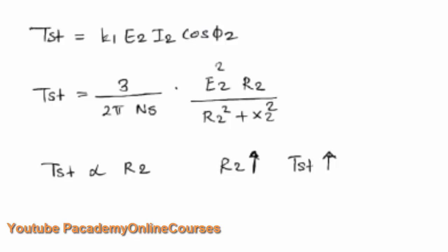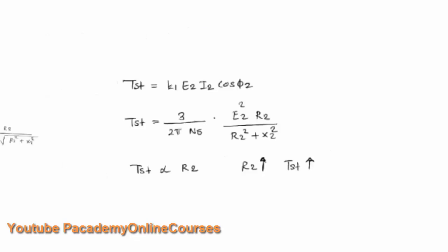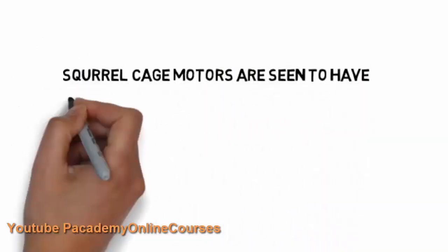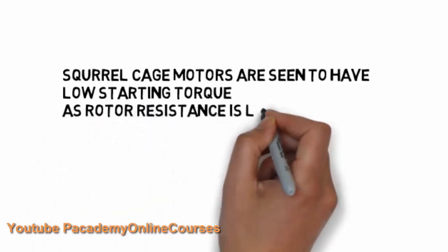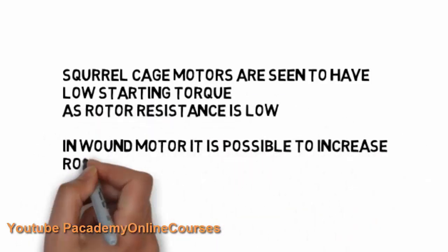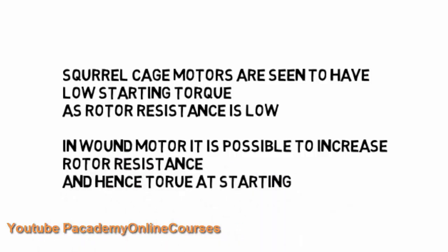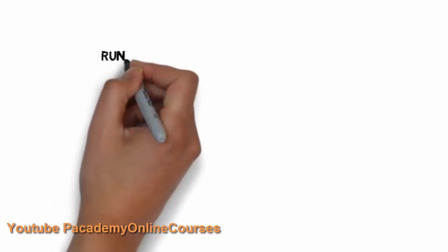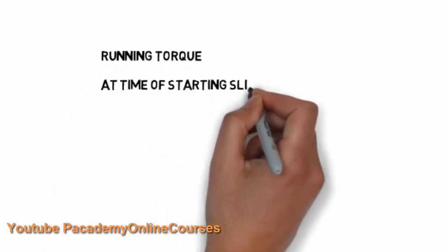The starting torque is directly proportional to the rotor resistance. In a slip ring induction motor, increasing the rotor resistance during starting increases the starting torque. Squirrel cage induction motors have low starting torque because their rotor resistance is low. In wound rotor (slip ring) induction motors, it is possible to increase the rotor resistance and hence increase starting torque — this is one of the key application differences between the two motor types.